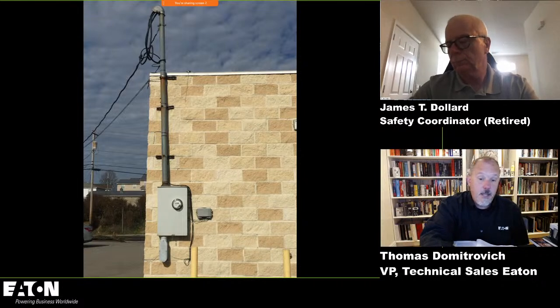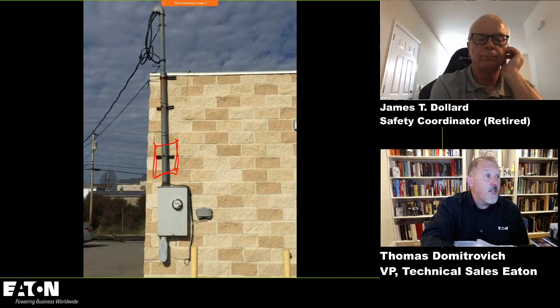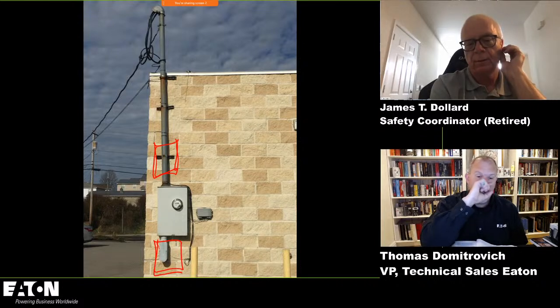And then you have this type of situation where you don't have a disconnect on the outside. And we made a change in 230.85 for an emergency disconnect. So an installation like this, where the main service panel's on the inside, is fine as long as it's not a 1 and 2 family dwelling. Yeah, that's right. This is not a 1 and 2 family dwelling. That's true. But if this was, then I would need a disconnect here, which could be a meter disconnect. And that would be permitted. Yeah, I could put a disconnect there.